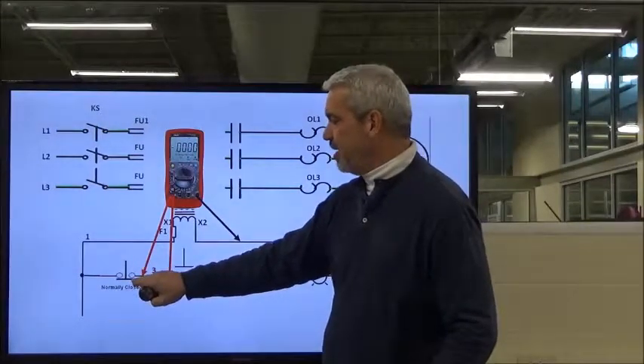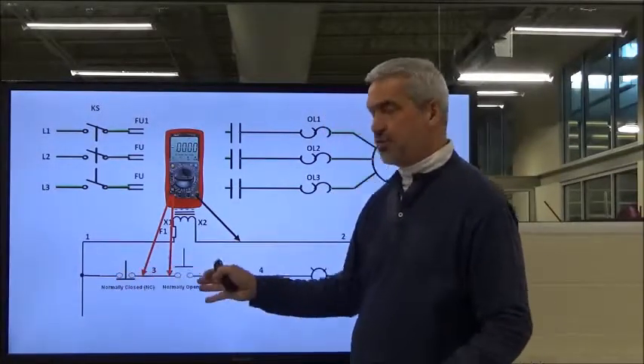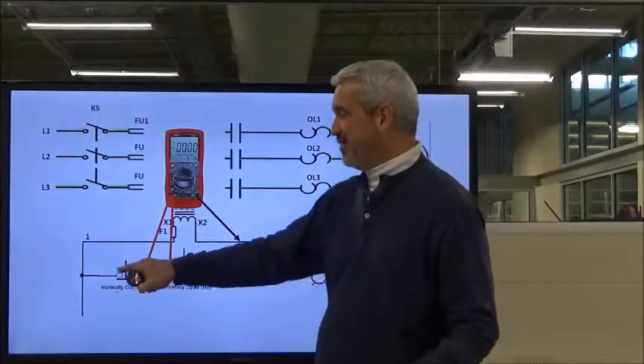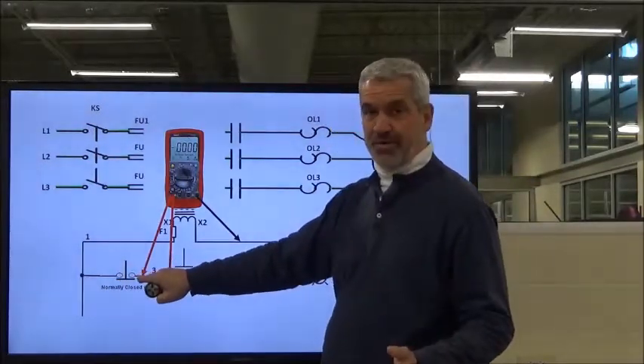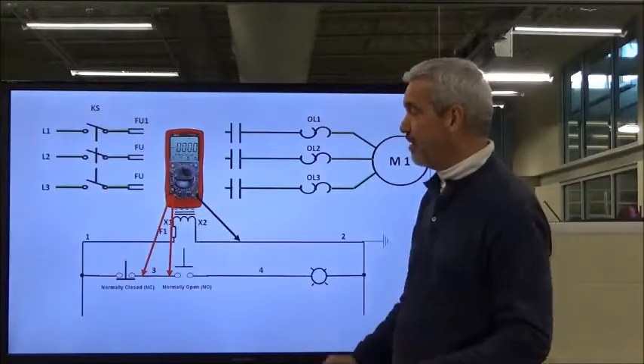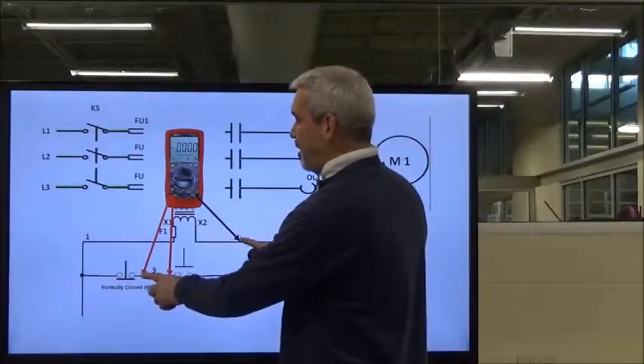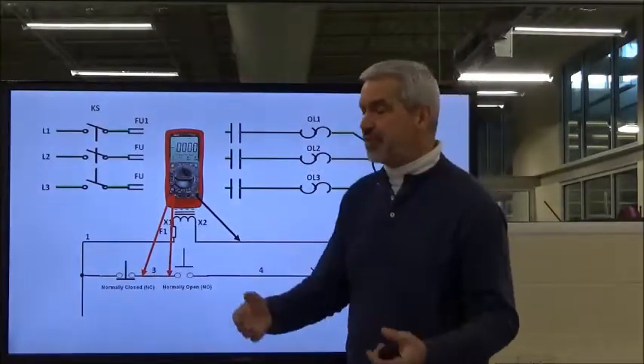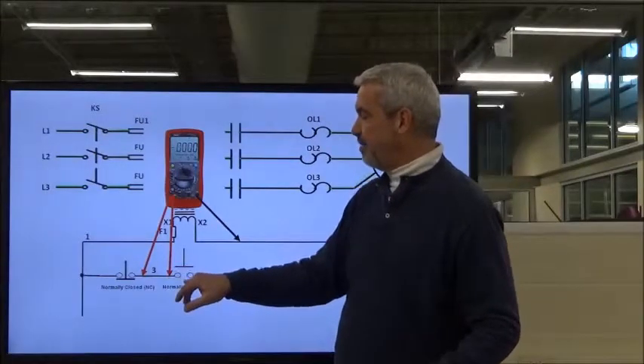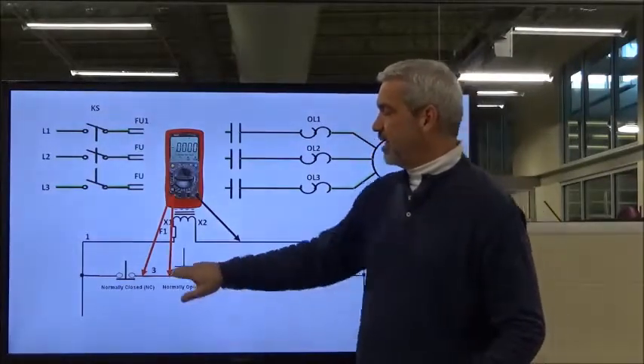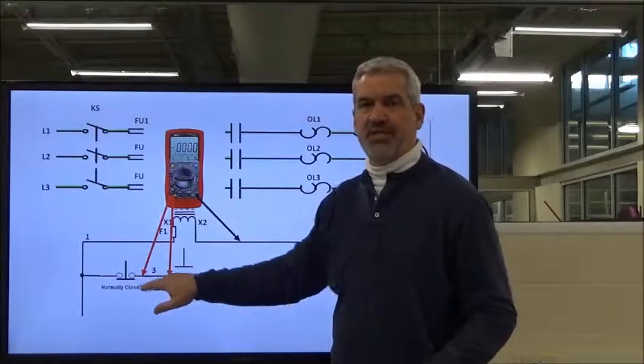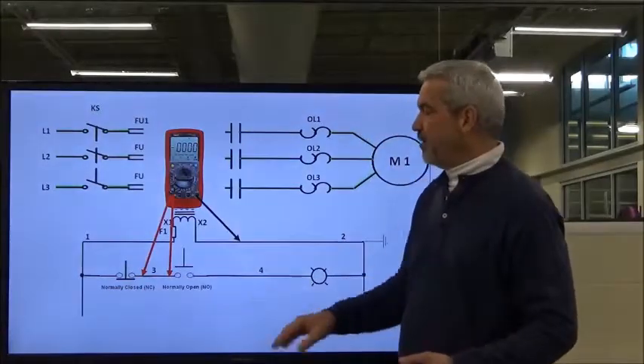I'm going to take my lead, put it right here, and see that it's passing through. This is a normally closed switch, so it theoretically should come right out with no interaction from me whatsoever. So I'm going to measure it right here. And then if I've got voltage there, I'm going to measure it right here too, because these two switches could be 50, 60 feet away, we don't know, and we don't know what happens in between.